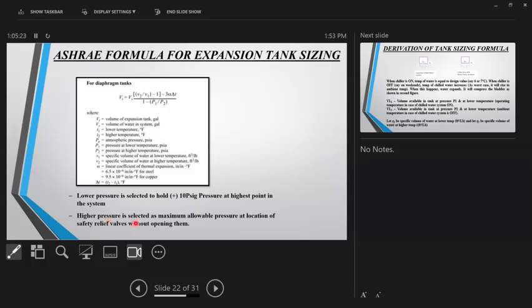The highest or higher pressure: if you select PN16 as the pressure rating, you obviously don't want the system pressures to go beyond PN16. So in that case, PN16 is the higher pressure. These two pressures are in the expansion tank. The lower pressure in the expansion tank is such that the pressure at the highest point is 10 psig. So 10 psig is not the pressure in the expansion tank. The lowest pressure in the expansion tank should be such that the lowest pressure in the system is 10 psig. How, we'll see later. Just keep in mind that the minimum pressure in the expansion tank should be such that the minimum system pressure is 10 psig above atmosphere.